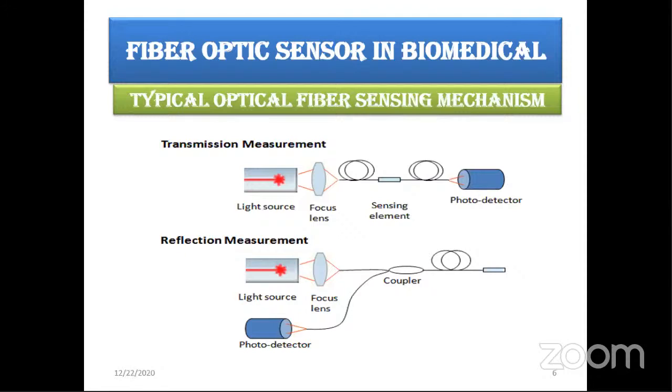Actually, the fiber optic sensor system consists of a fiber optic cable. Here we have that fiber optic cable, and it is connected to a remote sensor. In the second diagram, it is connected to the remote sensor. Either we can connect it to a remote sensor or an amplifier. We know that this fiber optic cable consists of a core surrounded by the clad material. The core is made up of either glass or plastic. We can place this sensor inside the cable, or we can place the sensor outside the cable. We can place this optical sensor near the source and detector, or it can be remotely placed anywhere. But based on the light characteristics given into this cable, this will be measured. The characteristics of the light will be measured by this sensor. This is the concept.